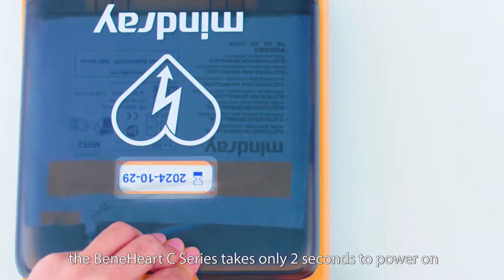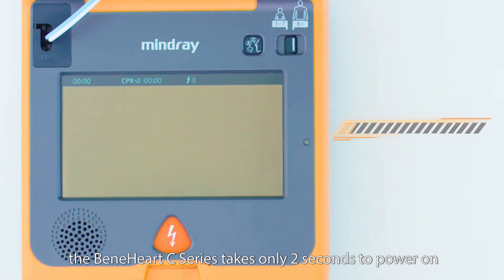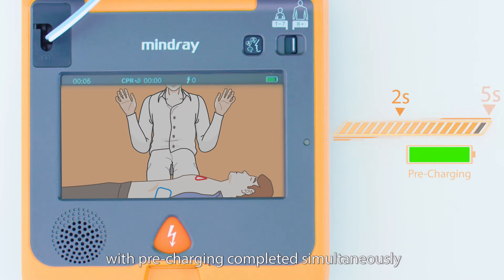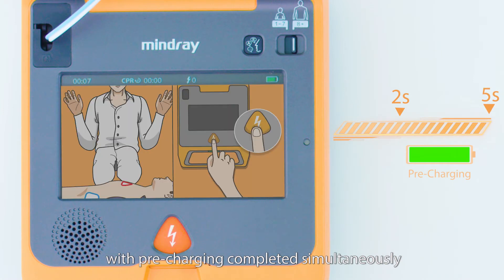Once the lid is opened, the BeneHeart C Series takes only two seconds to power on. The ECG analysis is shortened to five seconds with pre-charging completed simultaneously, increasing the chance of successful defibrillation.